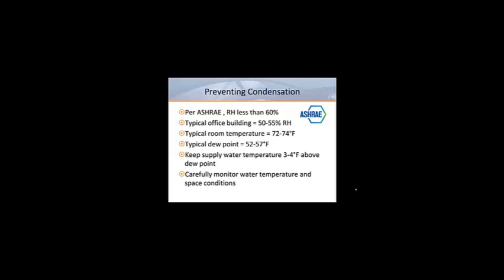In order to keep our cooling process sensible, it's critical that we prevent condensation from occurring on the beams. If we follow ASHRAE guidelines for good indoor air quality, we should keep the relative humidity of the room air below 60%. Most buildings operate at 50 to 55% relative humidity. At 72 to 74 degree room temperature, this corresponds to a dew point temperature of 52 to 57 degrees Fahrenheit. In order to prevent condensation, it's generally recommended that water temperatures should be 3 to 4 degrees Fahrenheit above the dew point. This means that the minimum water temperature should be 55 to 60 degrees Fahrenheit.